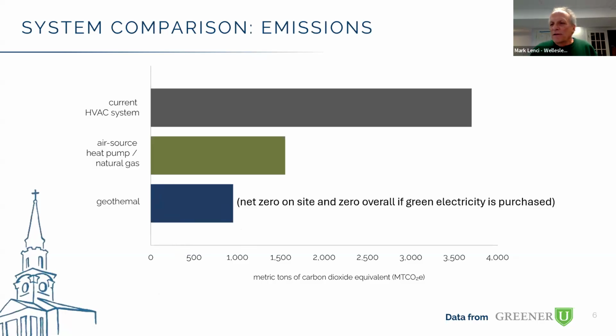The other thing we learned is, for those of you considering air source heat pumps — our well field, and I'll get to it in a minute, is almost 6 miles of piping underground to do this heat sink, with 18 850-foot wells. With air source heat pumps, you're going to have to get that same amount of energy out of the air.